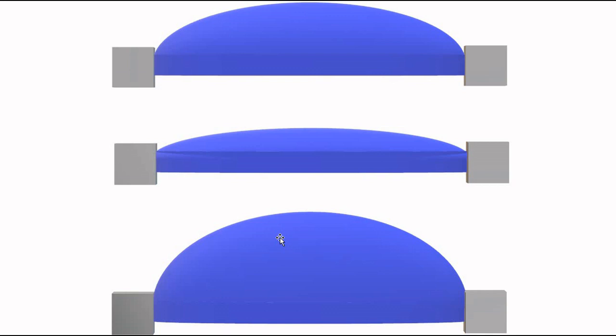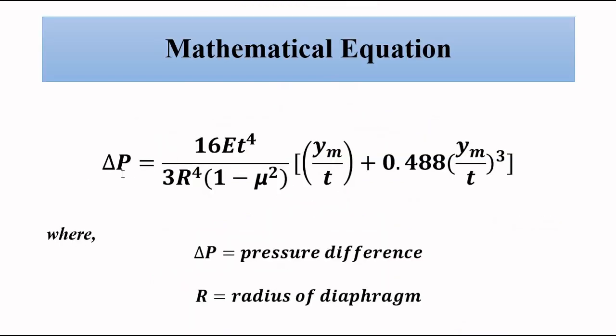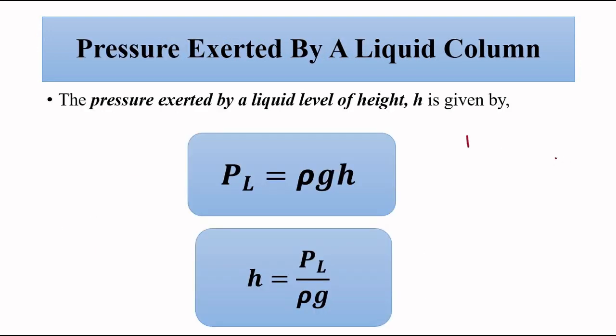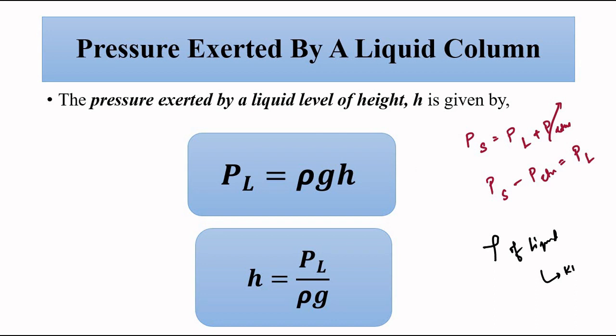depending upon the pressure on both sides, the diaphragm will either expand or get compressed. That will cause a linear displacement, and using this relationship we can determine the differential pressure. When the pressure on one side is known, the pressure on the other side can be calculated. So the total pressure measured by the sensor is the liquid column pressure plus the atmospheric pressure. The atmospheric pressure is constant, so we subtract it from the sensor reading, and that gives us the liquid column pressure. Here there is one important condition: the density of the liquid should be known.